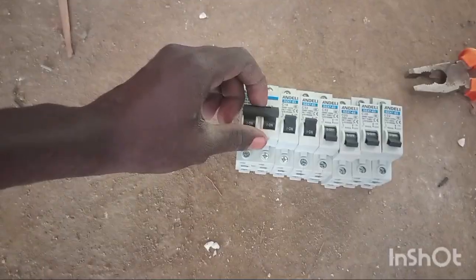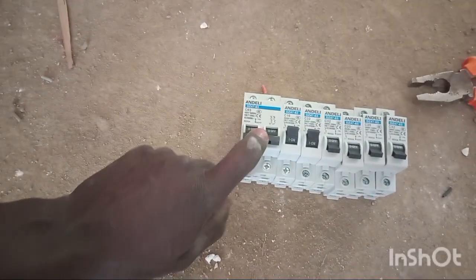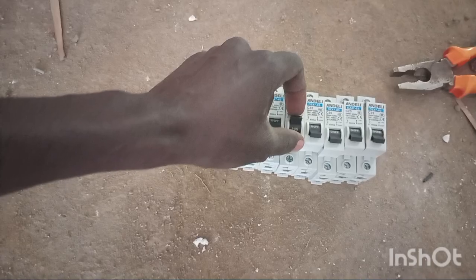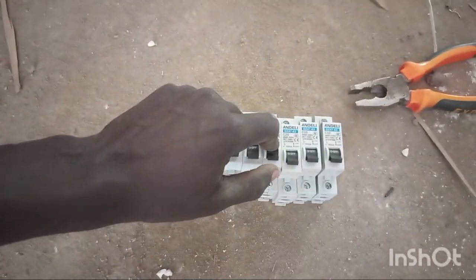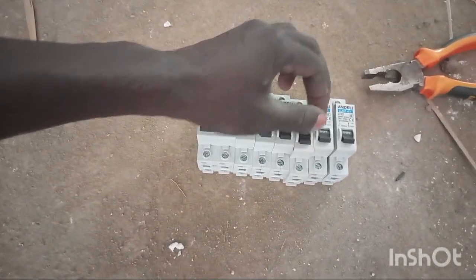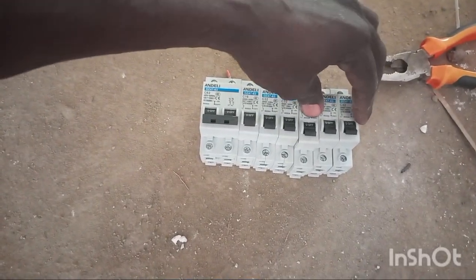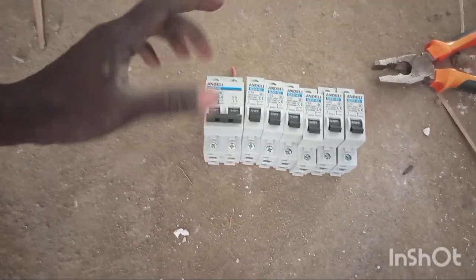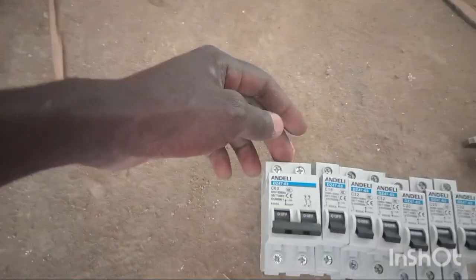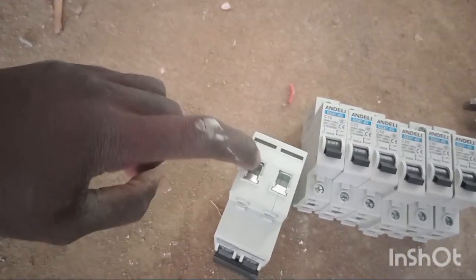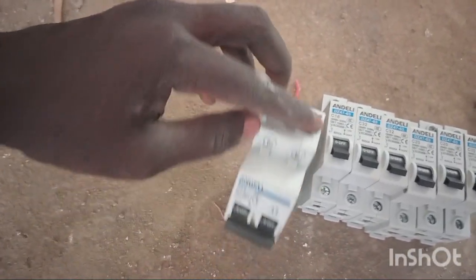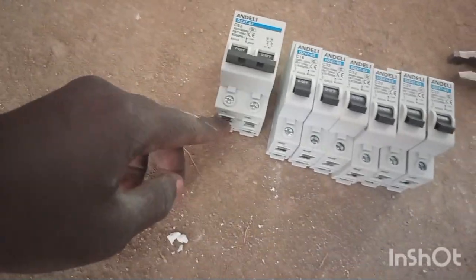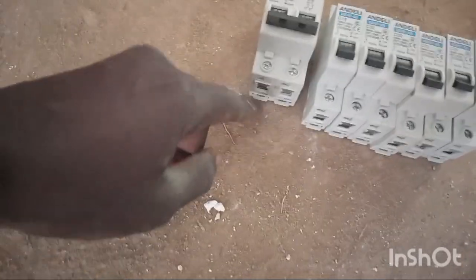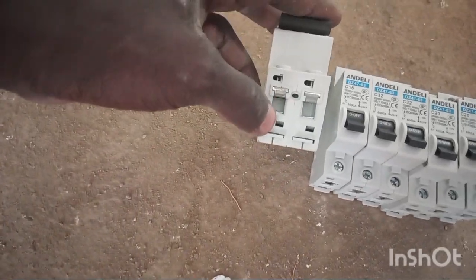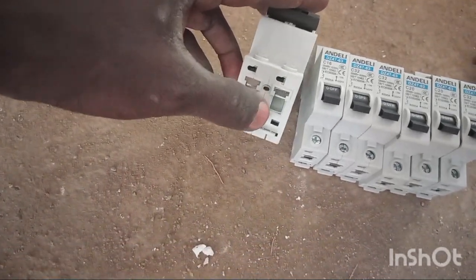So first, we are going to have the double pole. This is our double pole. Then we arrange from the cooker to the shower, 2 showers, then to the socket, then the lighting, 3 of them. That's how we are going to arrange. So when the sub main comes from the meter box, it will be connected in the upper side of the double pole here, the phase and the neutral. Then we are going to the load. Going to the load, it will be connected from the lower part of the double pole, phase and neutral.